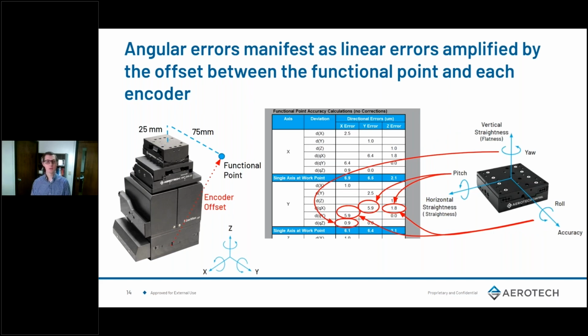So here's an example of where this becomes a problem. If you look at the left-hand side, I'm showing this red arrow that shows the offset from the encoder, the optical encoder embedded in the stage, to the functional point, which is your probe tip. On this particular system, that's almost 230 millimeters, which is a large offset. And you're amplifying all of your angular errors over that distance.